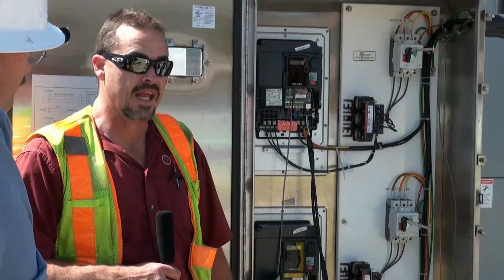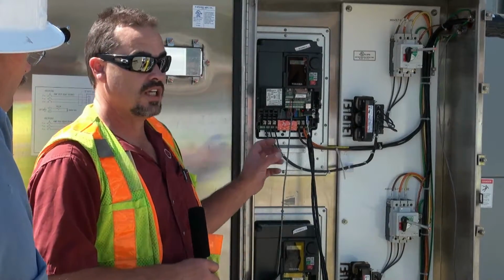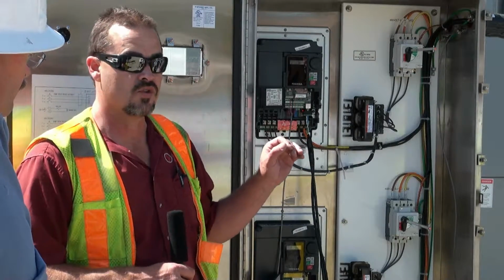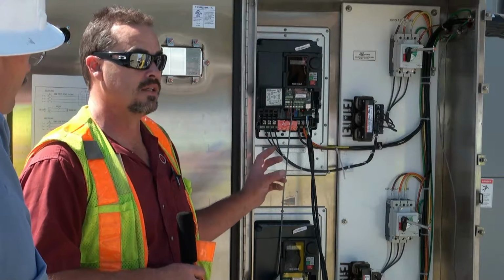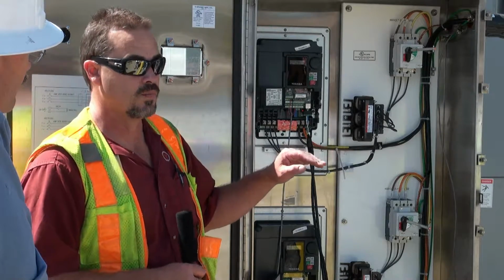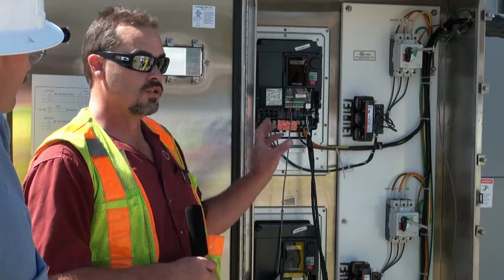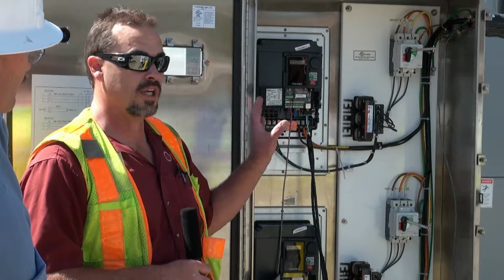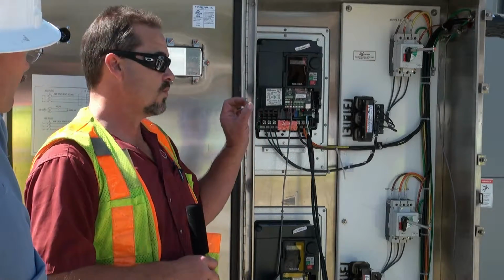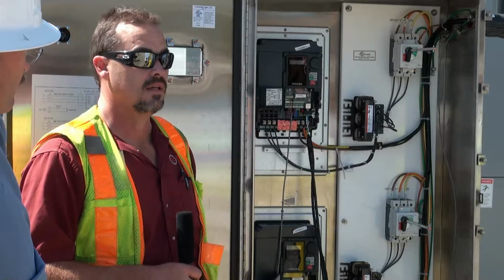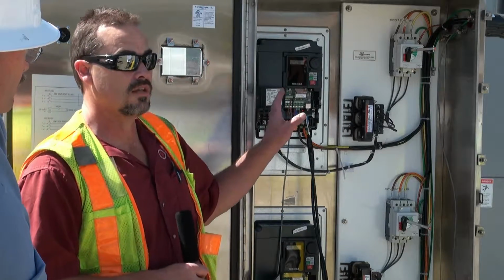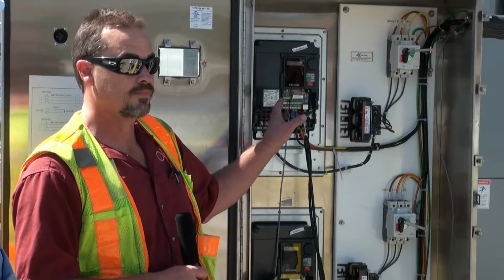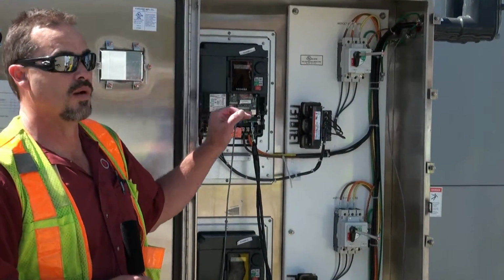If you put it in hand, you're changing the set point with the hand controls. You're not actually setting it to run at a certain speed. You're manually putting the drive on, and it's running off of the PID. So when you change the speed, you're actually changing the set point.